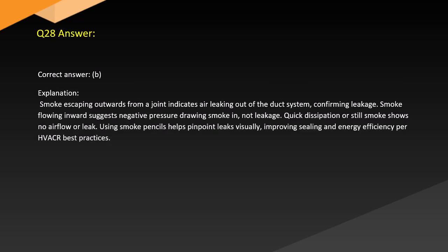Answer. Correct answer: B. Explanation. Smoke escaping outwards from a joint indicates air leaking out of the duct system, confirming leakage. Smoke flowing inward suggests negative pressure drawing smoke in, not leakage. Quick dissipation or still smoke shows no airflow or leak. Using smoke pencils helps pinpoint leaks visually, improving sealing and energy efficiency per HVACR best practices.